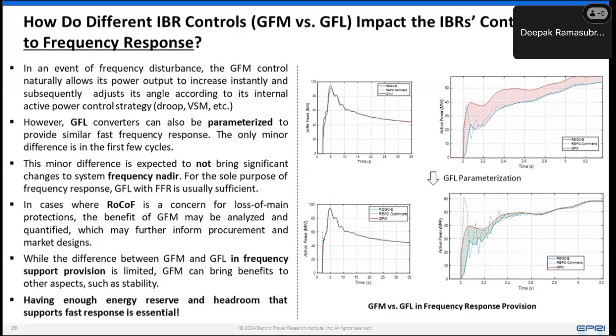So if you take a look at a synchronous machine plant and a synchronous machine, the red curve is the synchronous machine plant and the purple curve is the synchronous machine itself. You see that the machine's inertial energy injection is for the first 100 to 200 milliseconds. After that, the governor starts kicking in. So you are essentially only looking at that point in time to understand the difference. And if you compare that with grid forming versus non-grid forming with some form of fast frequency response, you can dig a little deeper and see that for the first 50 milliseconds, or first 3 or 4 cycles, you see a difference between the resources. But after that, they pretty much catch up quite well.